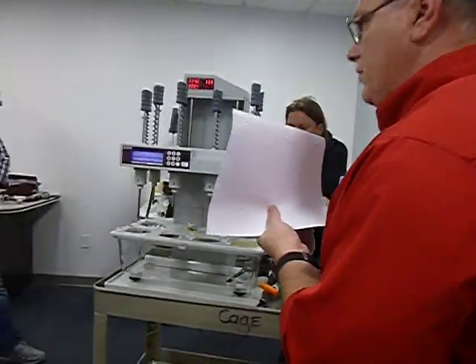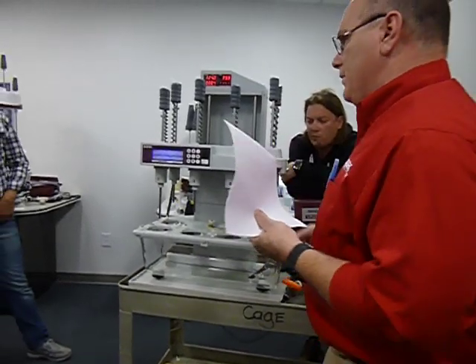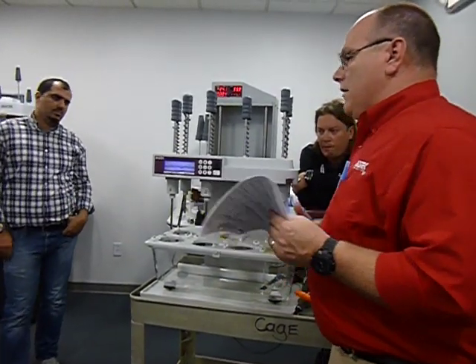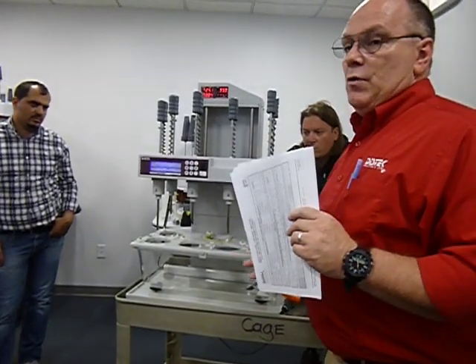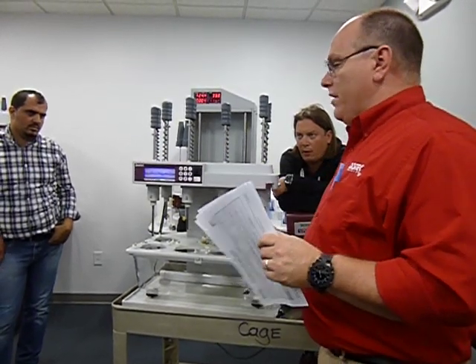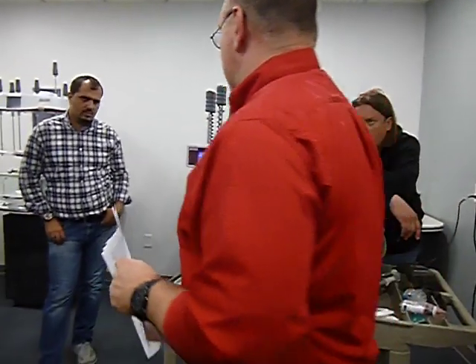.10, it says right on it. Okay, so it's a tighter tolerance. So you've got to check the low temperature and the high temperature, make sure the calibration probe is fine. And if that's not reading correctly, recalibrate it. First course of action. Still not reading correctly, it's going to be a replacement.